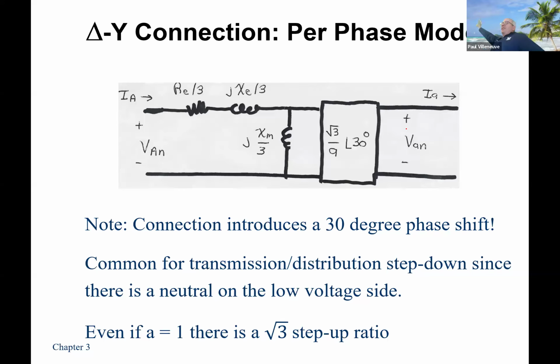Coming into the top of campus, we have, I believe, a delta-Y transformer that steps down from 46 kV to 4160. At the bottom of campus, it steps down from 1247 to 4160. So somewhere out in the system, they had to step down that 1247 from the 46 kV. So the bottom of campus cannot be connected to the top of campus because there's a 30-degree phase shift, just because of the additional transformation that happens at the lower part of campus. That's been a big issue for 30 years.